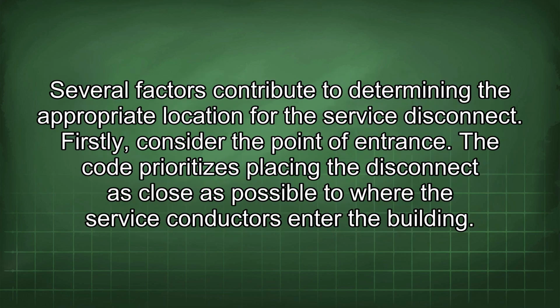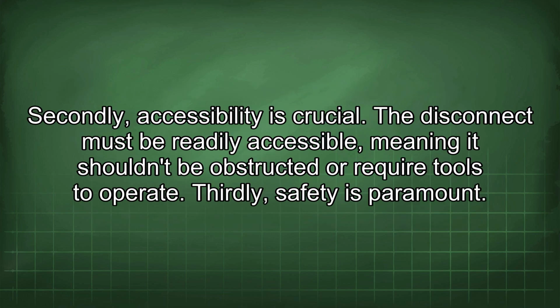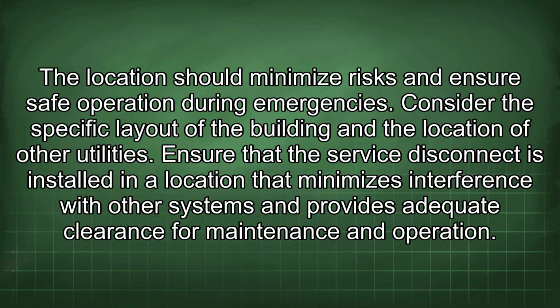Several factors contribute to determining the appropriate location for the service disconnect. Firstly, consider the point of entrance. The code prioritizes placing the disconnect as close as possible to where the service conductors enter the building. Secondly, accessibility is crucial. The disconnect must be readily accessible, meaning it shouldn't be obstructed or require tools to operate. Thirdly, safety is paramount. The location should minimize risks and ensure safe operation during emergencies.